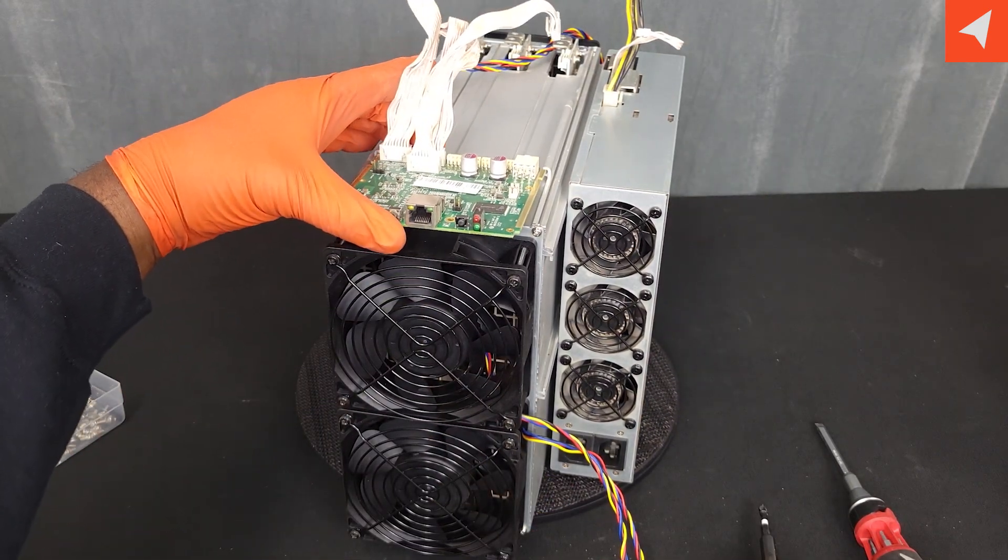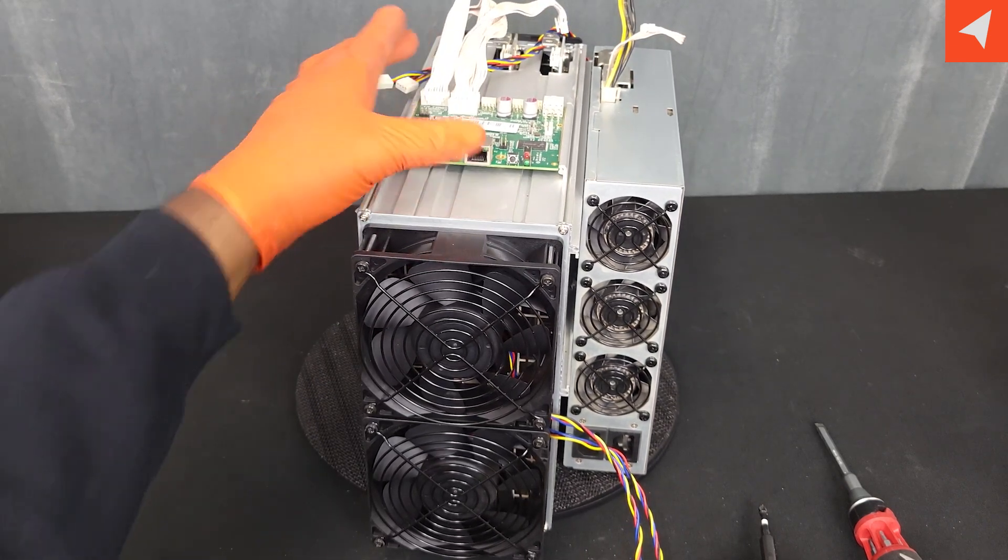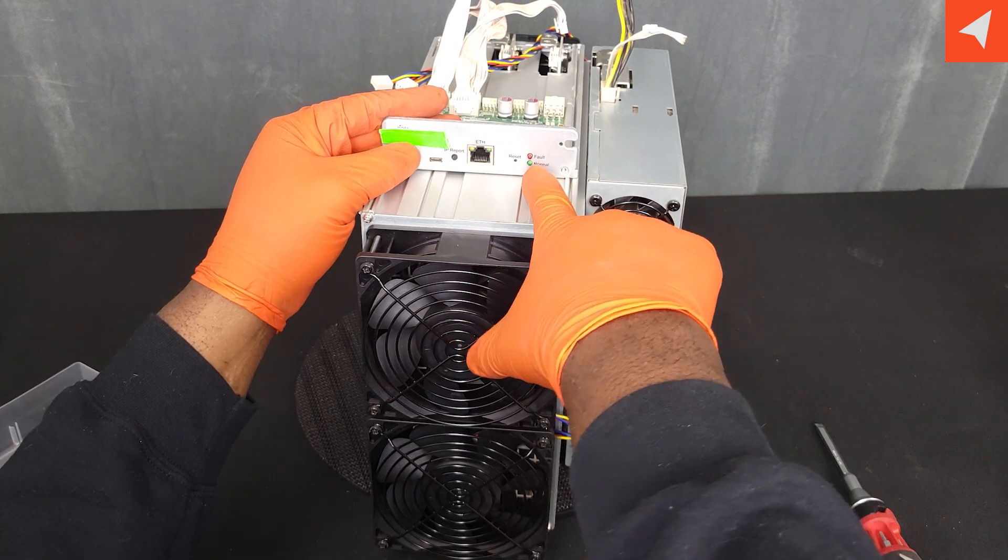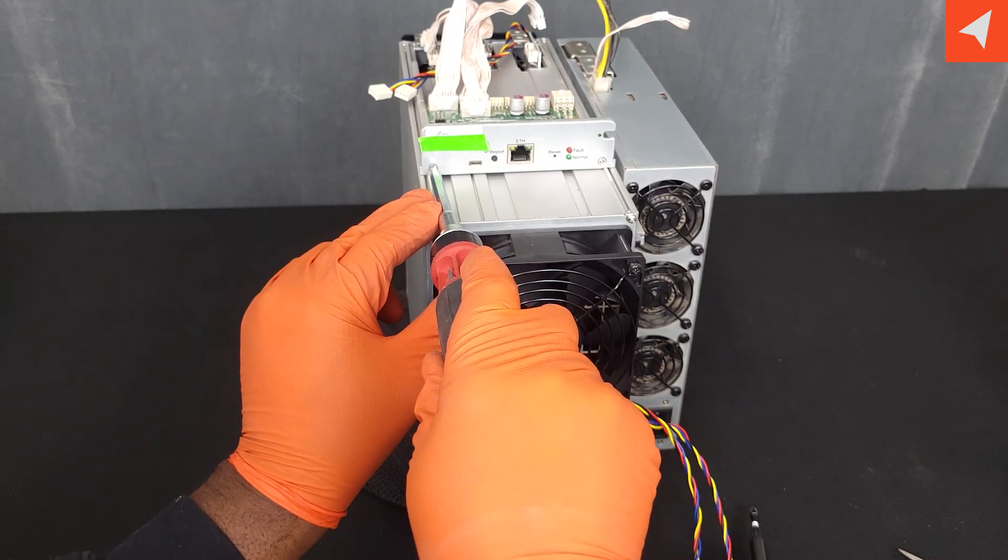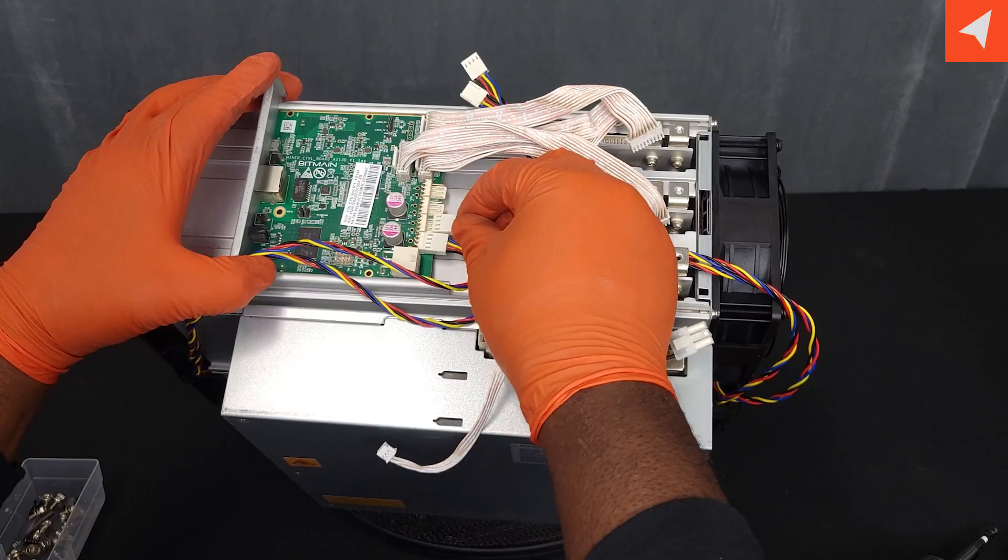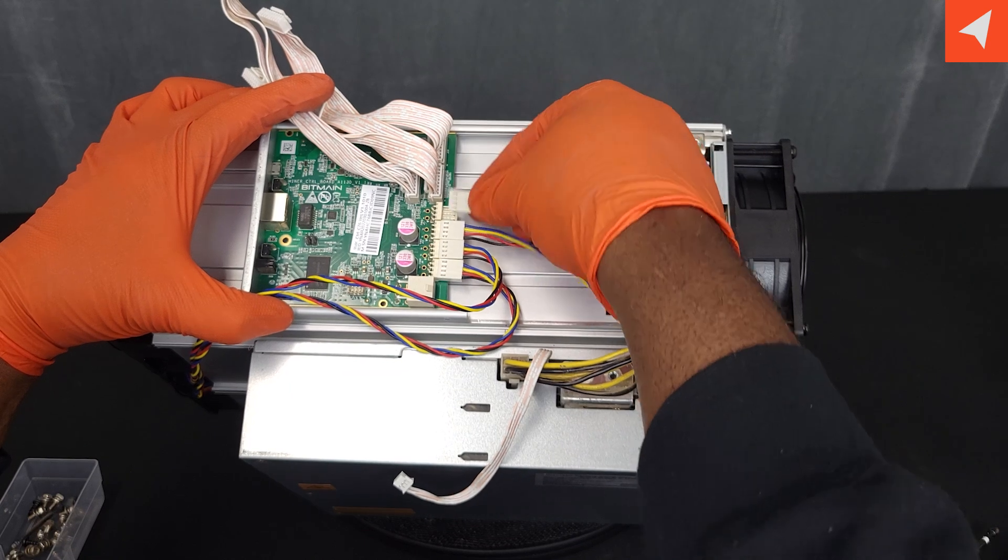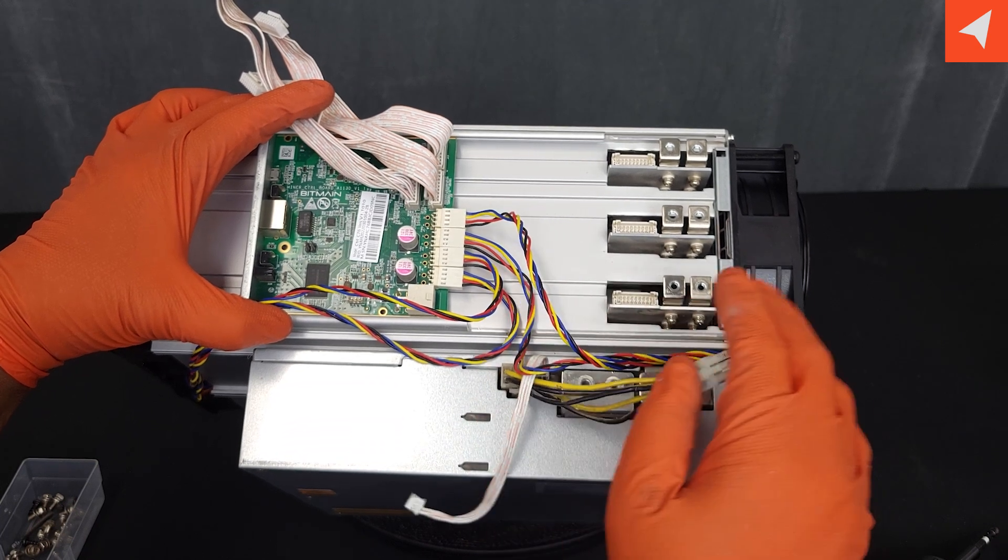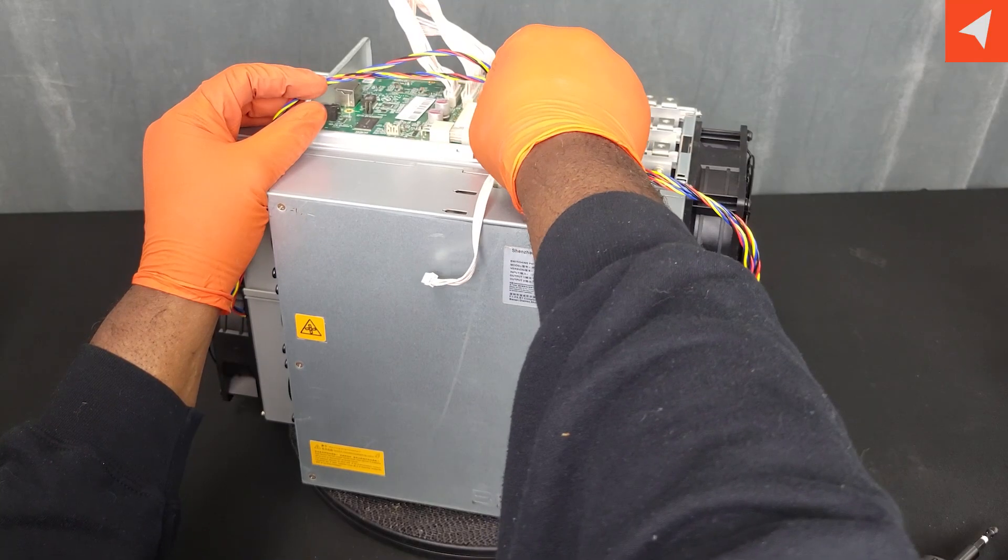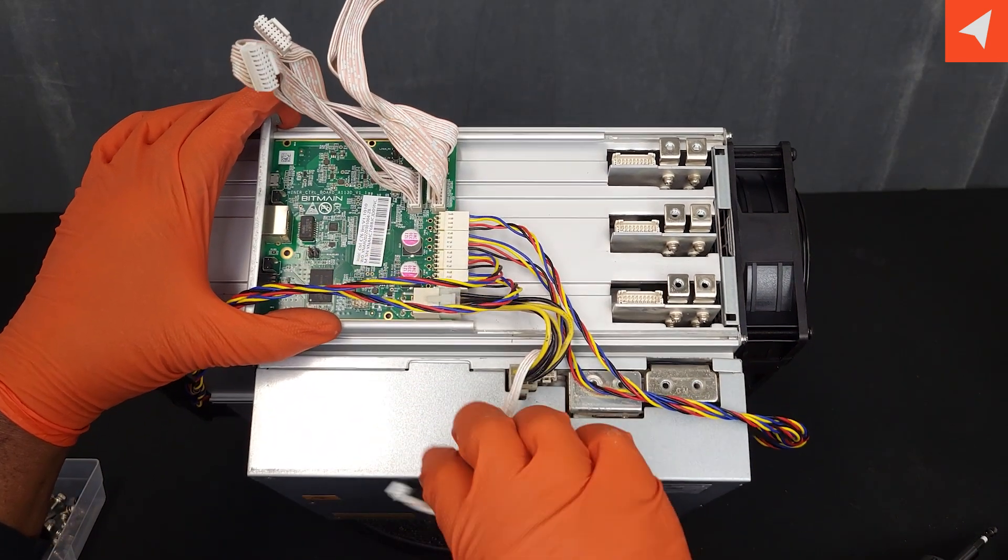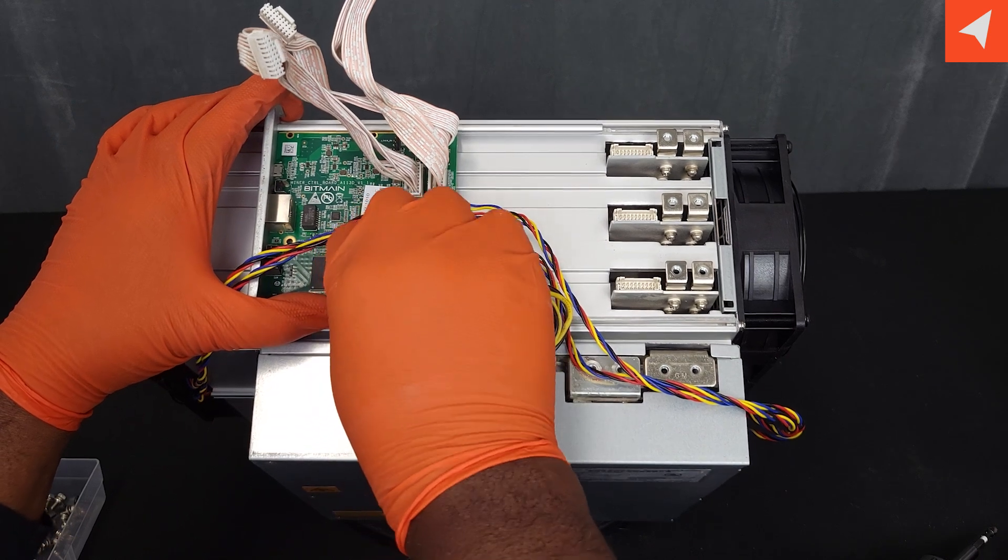Okay, let's go ahead and put in our control board and front face plate. This control board will go into these slots. Slide it all the way back, and then our face plate. Make sure to line it up with everything. Let's go ahead and string up our cables for our fans. So typically our fans in the front are going to go into the first two slots on our control board. And then our rear fans go into these slots here. The other thing to remember for these rear fan cables, we want them to go into this little channel in between the power supply and your main chassis. Let's go ahead and put in our power cable from the power supply to the control board.